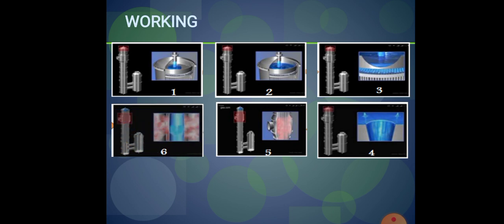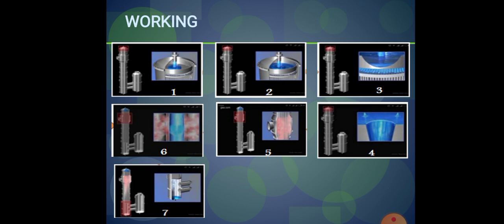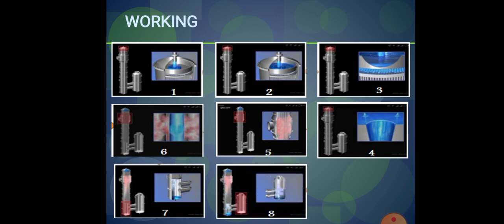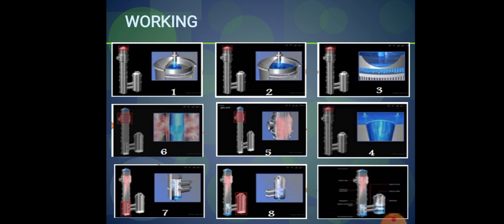In this falling film evaporator, heat is transferred from steam to the liquid through conduction through the walls of the tubes and through convection. When this heat is absorbed by the liquid in the tubes, the liquid starts to boil and vapors are formed. The vapors and concentrated liquid run downward, the liquid concentrates during the journey from top to bottom, and at the bottom the cyclone separator separates the vapors from the concentrated product.